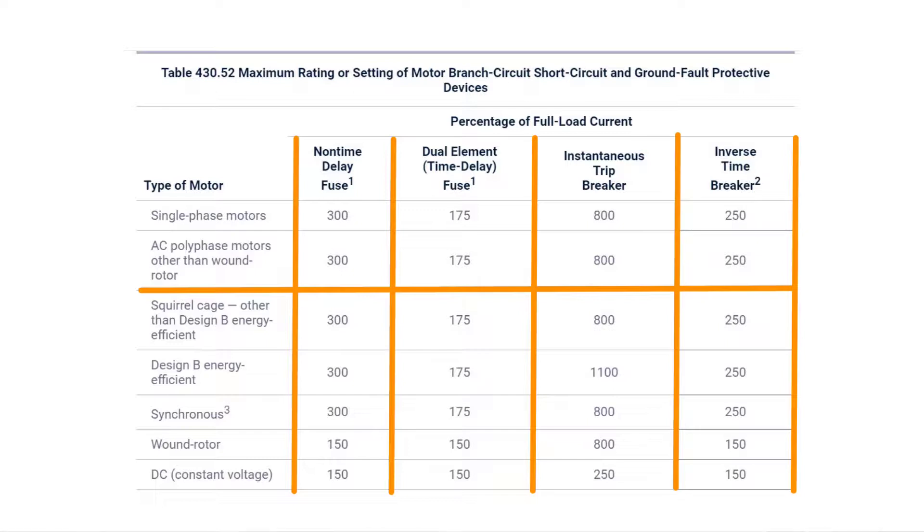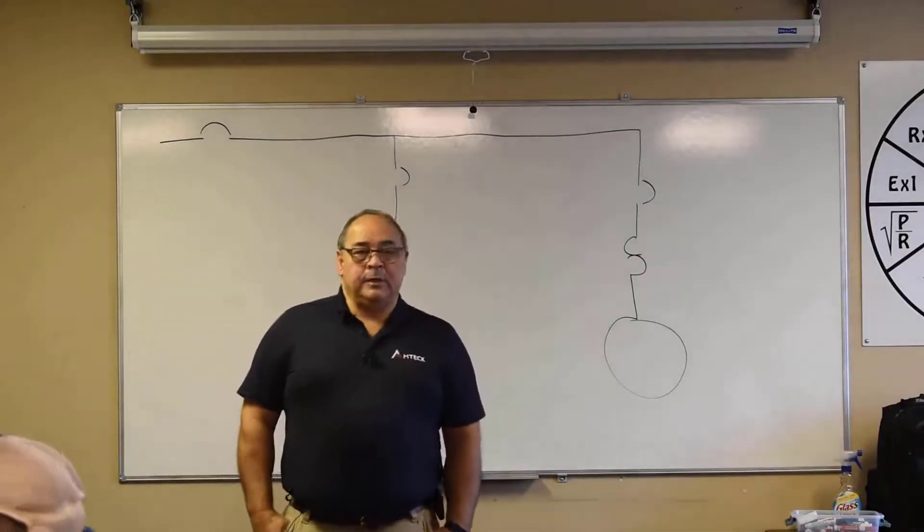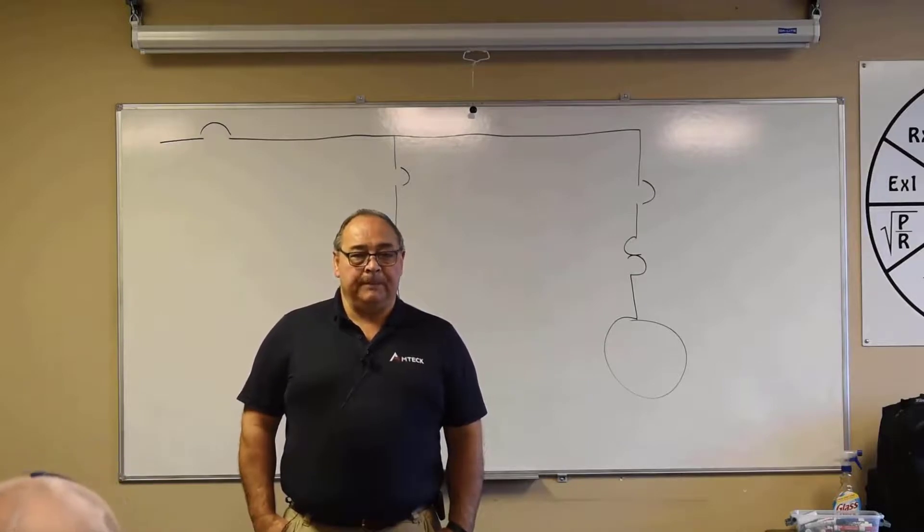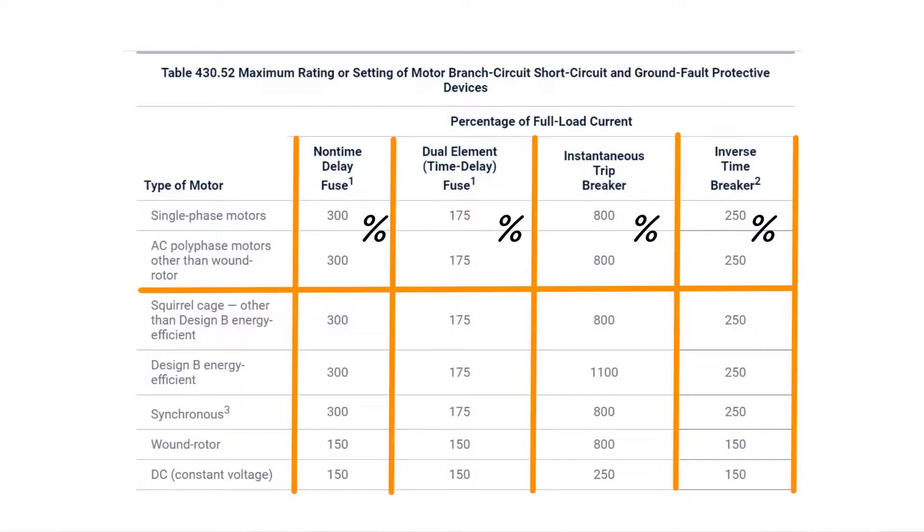Now I do want you to know that these are percentages, and we've got a 300%, we've got a 175%, we've got an 800%, we've got a 250%. Draw a percentage sign beside those, that way you know those are percentages. So on your test question, it will tell you which type of these four different items you're going to be choosing from. It has to, but it won't tell you the amps of the motor. You've got to figure that out by using the table we just looked at.